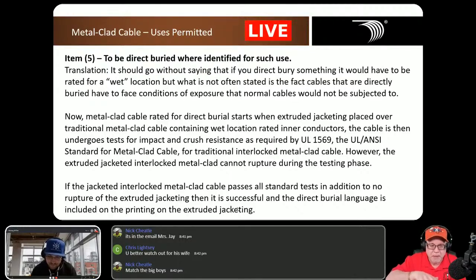It has to pass another element called crush and cover testing, passing UL 854, and those tests fall under UL 2556, a collection of tests we as manufacturers have to do. To be direct burial rated, it has to be tested and pass the same tests as normal MC, except it gets bumped up to 2,000 pounds of crush, and that crush cannot rupture the PVC jacket over it. So it can crush down, but you can't find any ruptures in the actual extruded membrane.